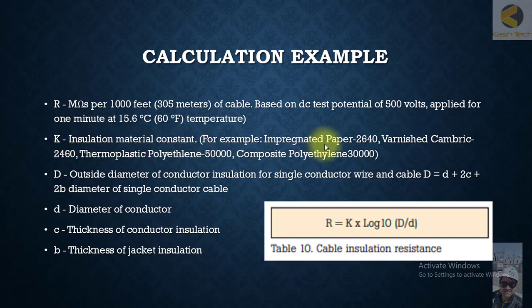K is the insulation material constant. For example: impregnated paper is 2640, varnished cambric is 2460, thermoplastic polyethylene is 50,000, composite polyethylene is 30,000.